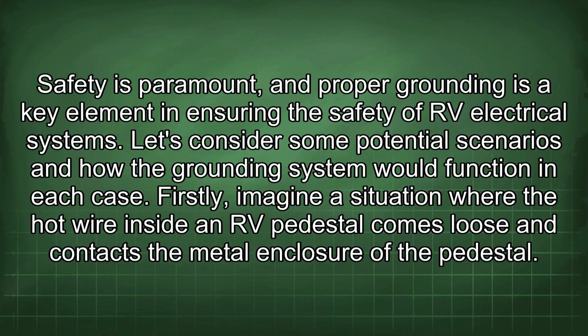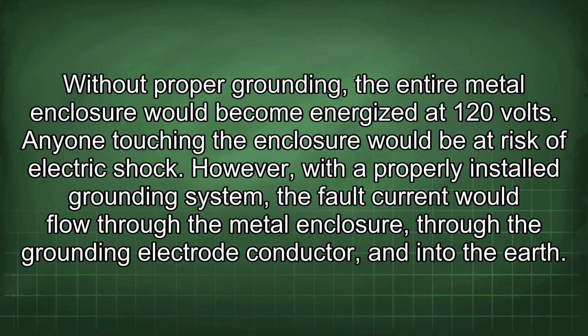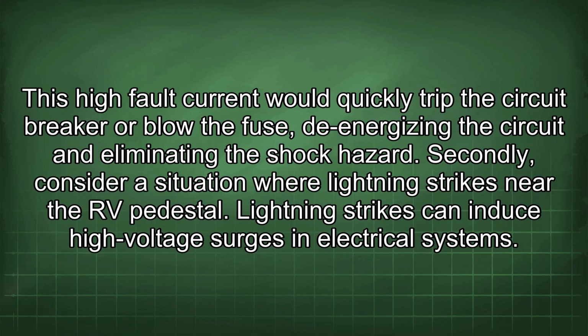Let's consider some potential scenarios and how the grounding system would function in each case. Firstly, imagine a situation where the hot wire inside an RV pedestal comes loose and contacts the metal enclosure of the pedestal. Without proper grounding, the entire metal enclosure would become energized at 120 volts. Anyone touching the enclosure would be at risk of electric shock. However, with a properly installed grounding system, the fault current would flow through the metal enclosure, through the grounding electrode conductor, and into the earth. This high fault current would quickly trip the circuit breaker or blow the fuse, de-energizing the circuit and eliminating the shock hazard.